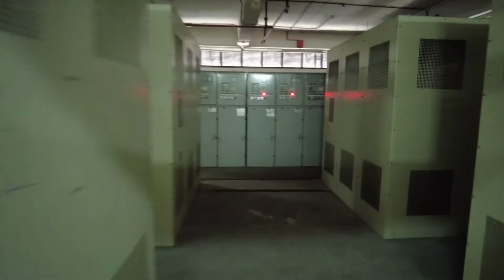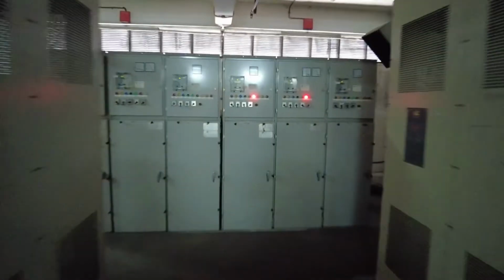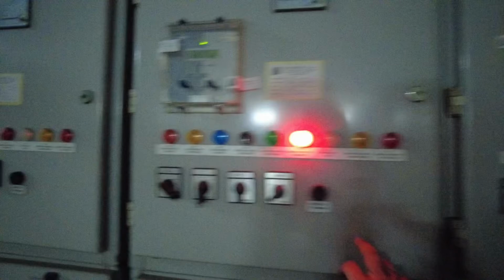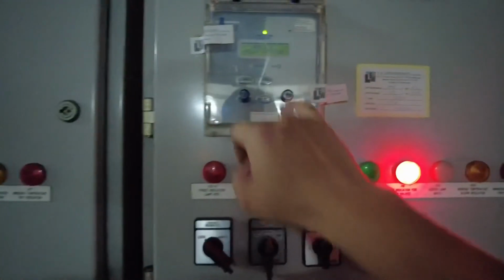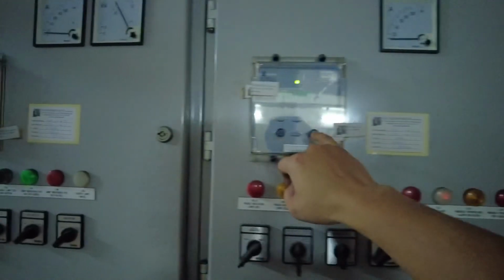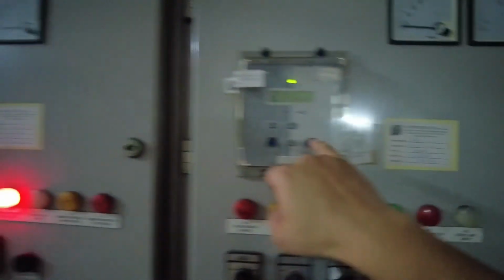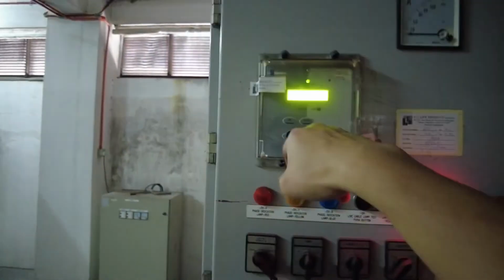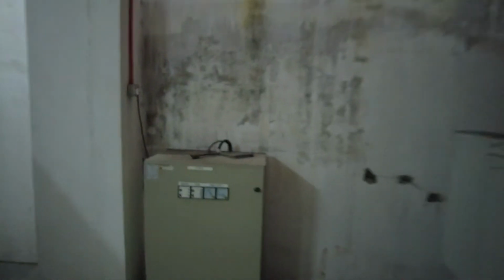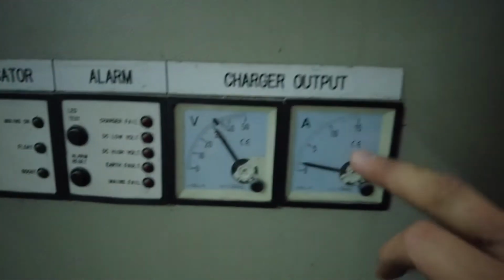Let's check the BCB panel. This is a BCB panel. Heater all is in good condition. Protection relay is in good condition. Then here we have the tripping unit. Make sure voltage is okay. Charger is operating.